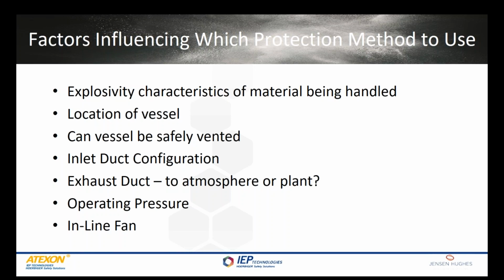So please do not get caught in the trap of hearing that, oh, I just have an ST1 dust. It's not as severe as the others, so I don't have as much of a risk. That's really not the case at all. All that ST value tells us, who design protection methods using the KST value, is how much time we have to react to an explosion. Whether it's a KST 190 or a KST 90, that tells us how much time we have to react. As the end user, who's going to have this vessel that is equipped with this explosion protection method, whether this explosion happens in 200 milliseconds or 400 milliseconds won't matter to you. You're still going to have the explosion. It's still going to cause significant damage. So don't get caught in the trap of I don't have an explosion threat because I just have an ST1 dust.